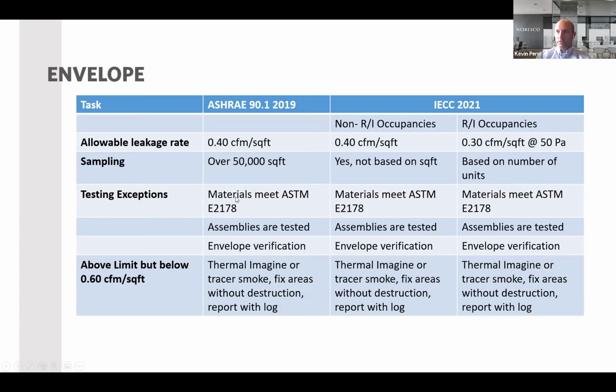So you could say your materials are spec'd to meet the ASTM standard. You test some air barrier component assemblies, and then you also do some envelope verification. They might be asking, what is envelope verification? Envelope verification is, by definition in the code, installation inspections and deficiency logs, or logs for corrections.